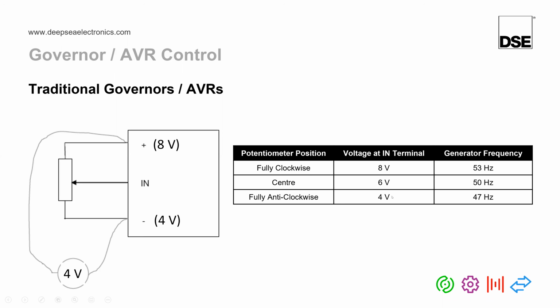The reason it's 4 volts is because the lowest voltage here is 4. The reason it's 8 volts is because the highest voltage here is 8. And the reason it's 6 volts in the center is because 6 is halfway between 8 and 4. The varying voltage on this IN terminal then tells the governor or AVR what voltage or frequency the generator should be run at.